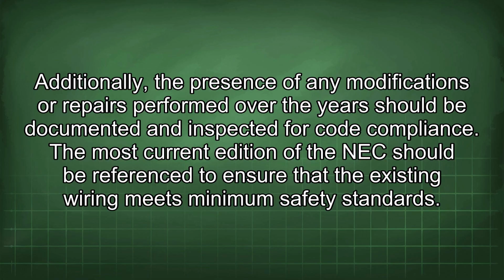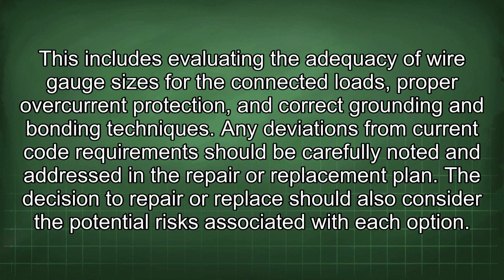for code compliance. The most current edition of the NEC should be referenced to ensure that the existing wiring meets minimum safety standards. This includes evaluating the adequacy of wire gauge sizes for the connected loads, proper overcurrent protection, and correct grounding and bonding techniques. Any deviations from current code requirements should be carefully noted and addressed in the repair or replacement plan. The decision to repair or replace should also consider the potential risks associated with each option.